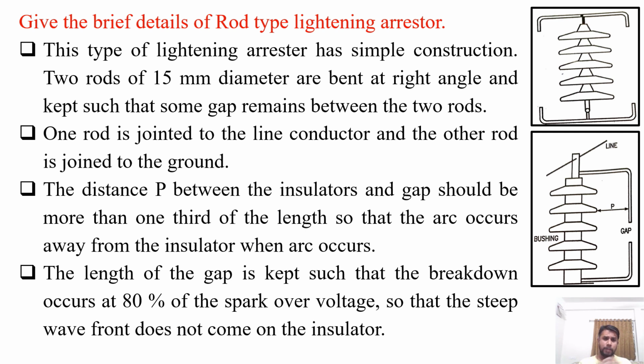So, this type of lightning arrester has a simple construction. Two rods of 15 mm diameter are bent at a right angle and kept such that a gap remains between the two rods like this. These two rods are kept bent at a right angle, either like this or like this. So either type of construction is possible. This is for the transformer protection case. This is for the transmission line protection case.